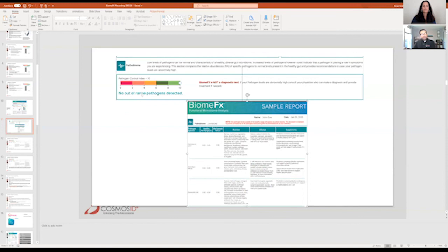And then I have to show the FDA in 100 people or 1,000 people, depending on how they power these studies, who don't have C. diff, and these people are confirmed by a previously approved methodology, that my method is not going to accidentally pick up C. diff, right? And then you have to do this like 3 or 4 times in a row. So you have to do all of this validation, and you have to go through these approvals if you want to be a diagnostic test.